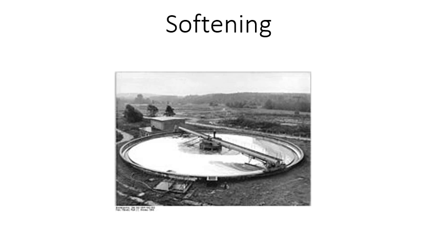So recarbonation. If the pH is now lowered, the precipitation of calcium carbonate and magnesium is improved, along with allowing the excess lime to settle. Recarbonation is usually a two-step process. First, reduction of the pH to 10.4, which encourages the precipitation of CaCO3 and Mg(OH)2, then reducing the pH to 9.8 or less to encourage non-carbonate hardness to precipitate.